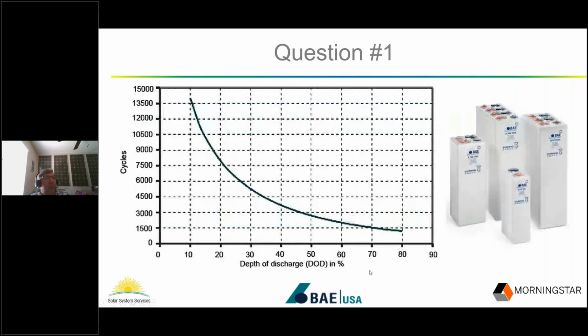There are also advanced technology batteries out there now, newer ones. This is the BAE battery, a tubular plate one—their tubular plate gel, the OPzV. You'll note this battery can cycle 1,500 times to 80% DoD. That's just 80%, almost 1,500 cycles, which is quite substantial. And if you look around the 15% range, you're looking at over 10,000 cycles. So again, yes, you can discharge it to 80% depending on the better technology and the manufacturer. 1,500 cycles is a lot—about 3 years or more of discharging it deeply every day.